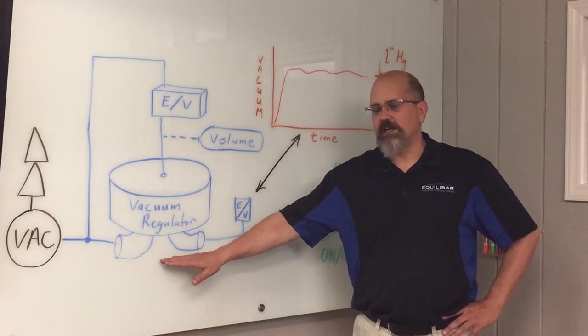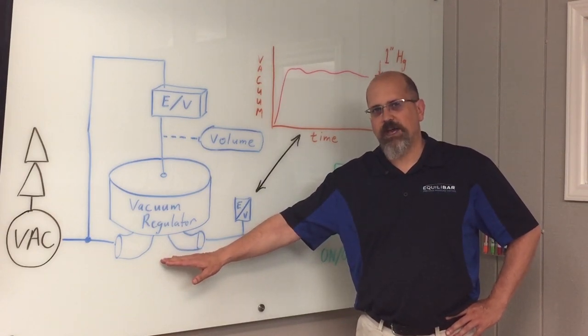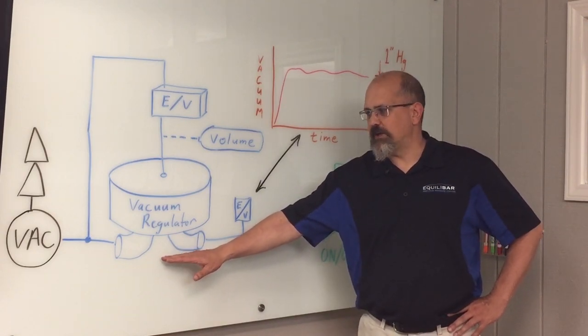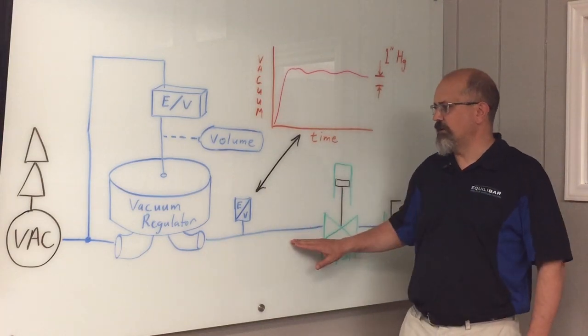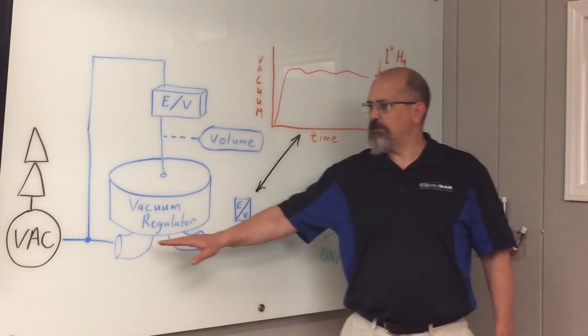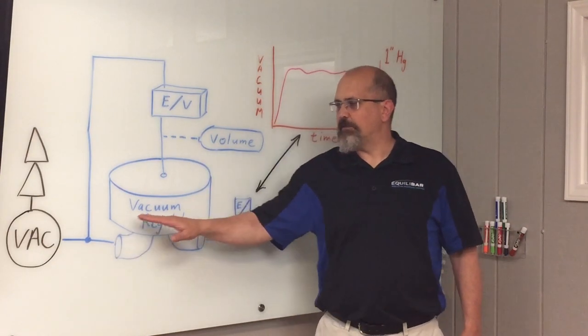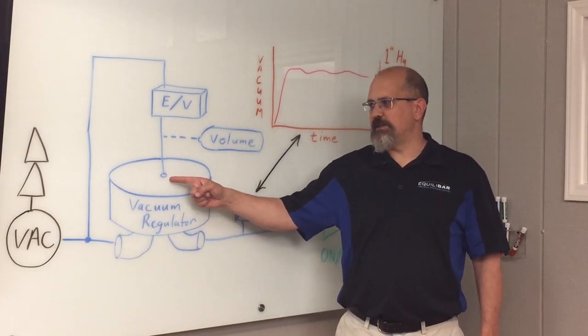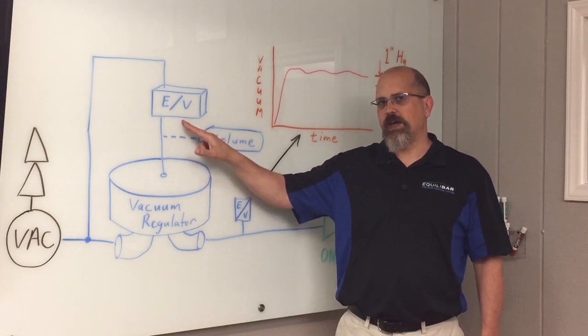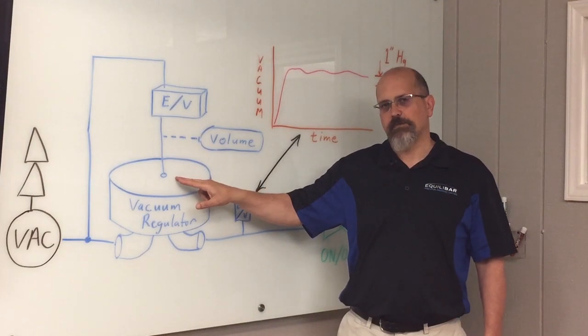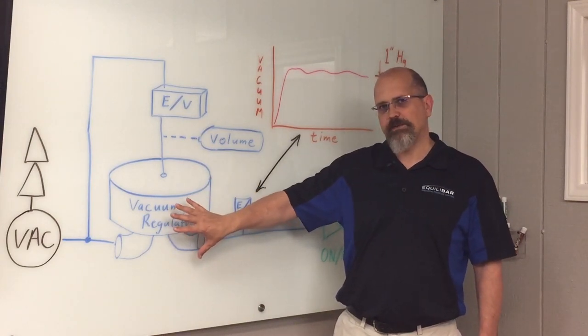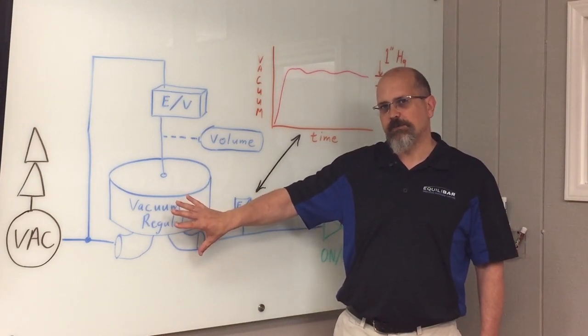The main thing we're looking at is this high-speed fast response vacuum regulator. This vacuum regulator is controlling the pressure here. It's connected to a vacuum supply here. It's a pilot-operated valve. It receives its pilot signal from an electronic vacuum regulator. It's a small black box you'll see connected to the pilot port of the large gray PVC high-speed vacuum regulator.